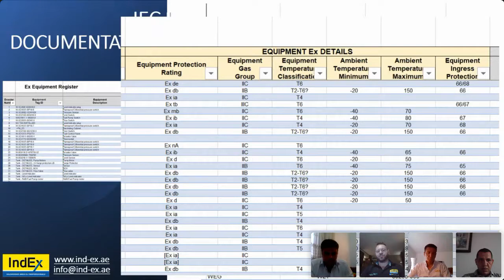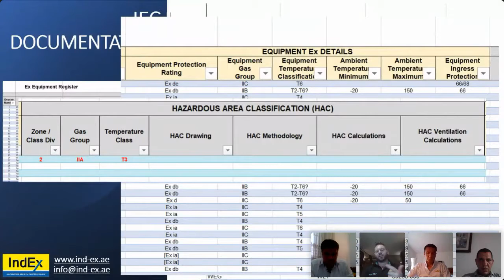You would then have the hazardous area classification, what it is rated for, and you do a gap analysis between the equipment and the classification. You make sure the equipment is safe for the area. You then have the details of the certification, the IECEx certificate. You make sure the equipment is not fraudulent, that it has not been pulled from the market due to safety reasons. So all this and conditions of use, very important.